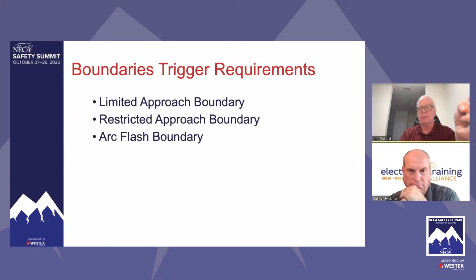And we're getting pretty close here. We're down to about 9 minutes. So there's a normal operating condition. I'm going to skip through this one because we went through that. The boundaries, okay, they trigger requirements. You've got a limited approach boundary, restricted approach, and arc flash boundaries.